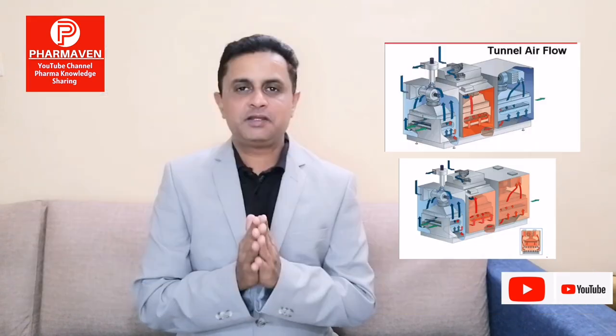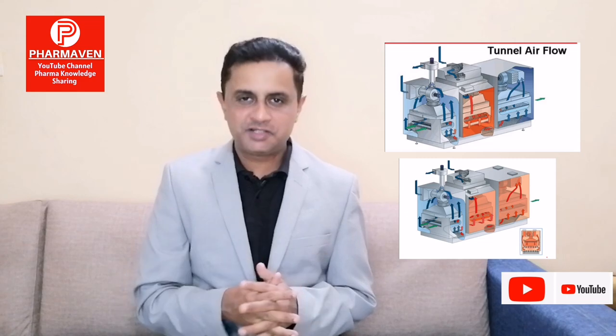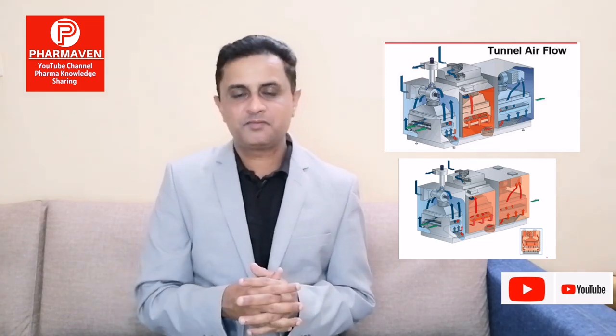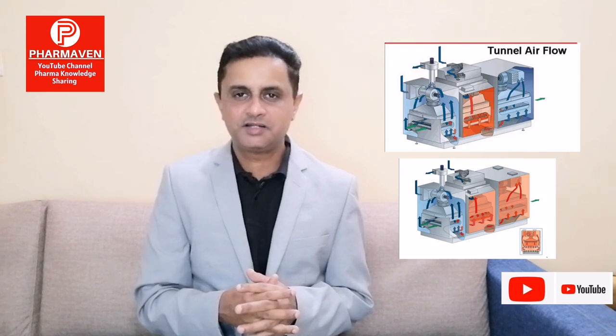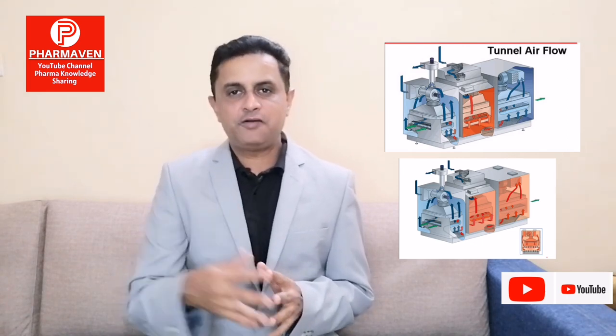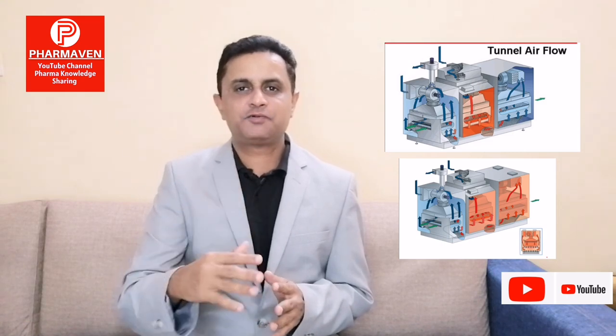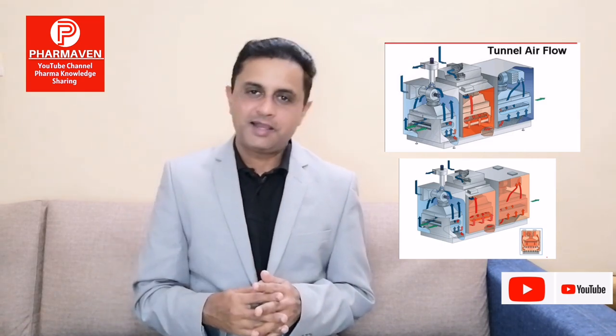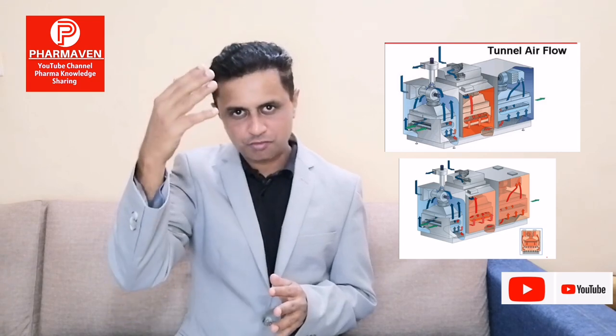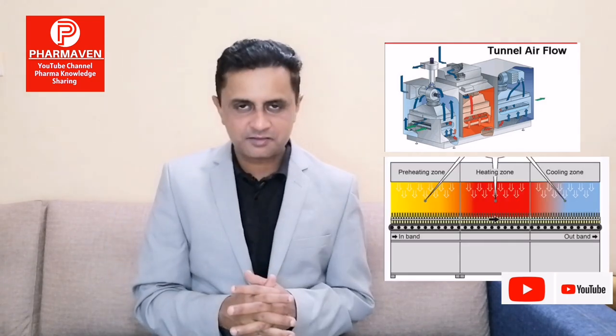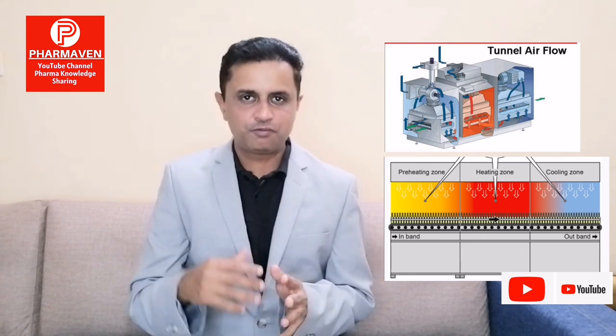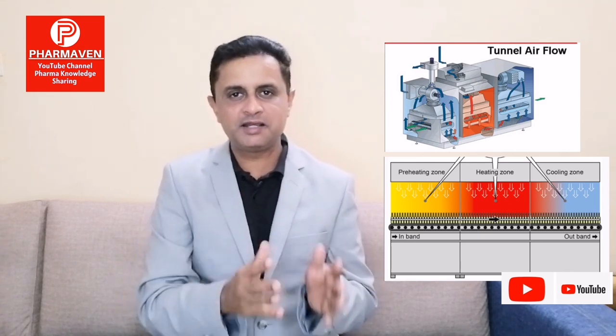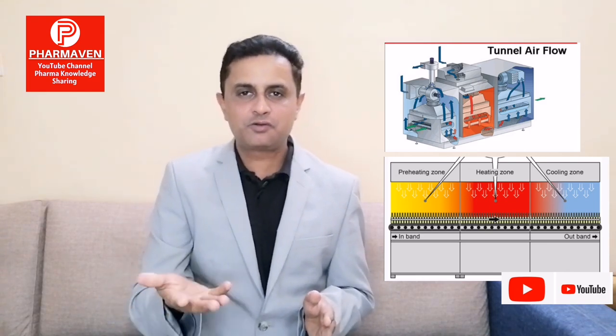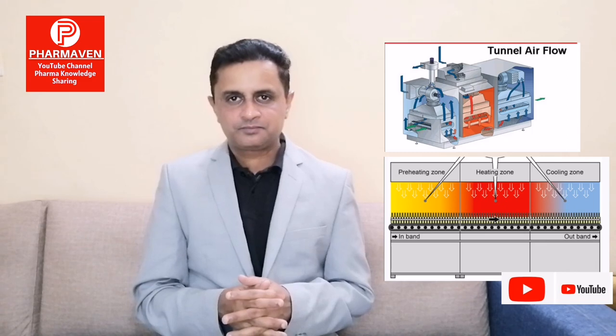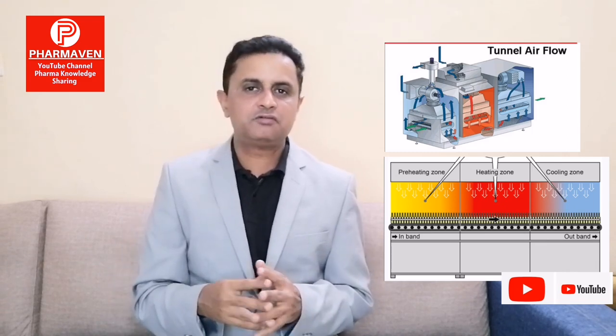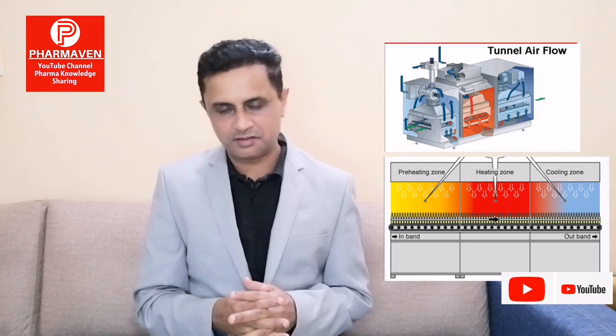In tunnel operation, in sterile filling operation, we first wash the vial, then it goes to the tunnel where it gets heated and depyrogenated. In the tunnel, the air travels to the heater banks, the air gets heated, and it is forced through the blower towards the vials. Through these forced convection currents, the heat is transferred from the heated air to the vials, which are comparatively cool inside the tunnel. So this is the principle of how heat is transferred inside the tunnel through convection currents.